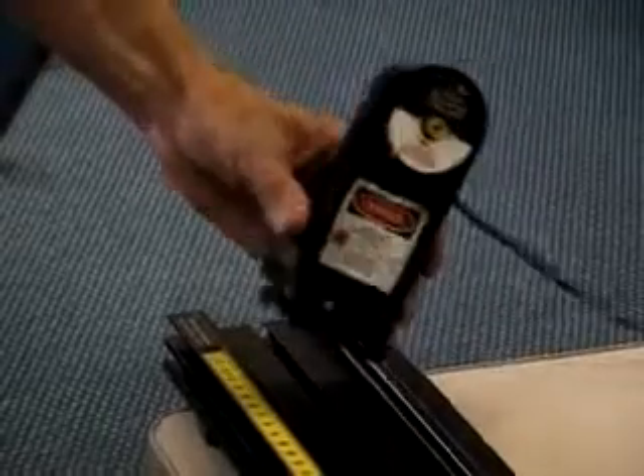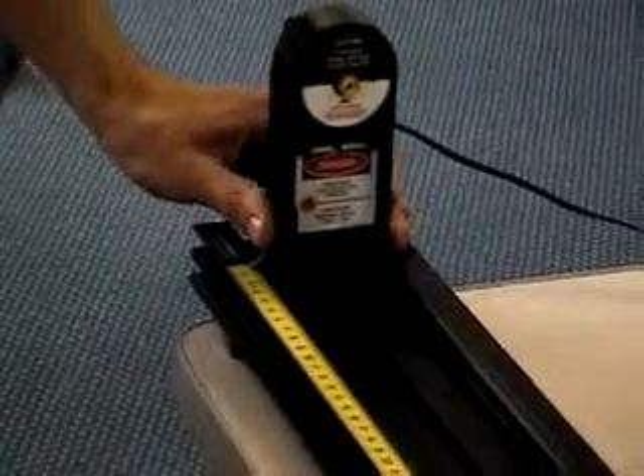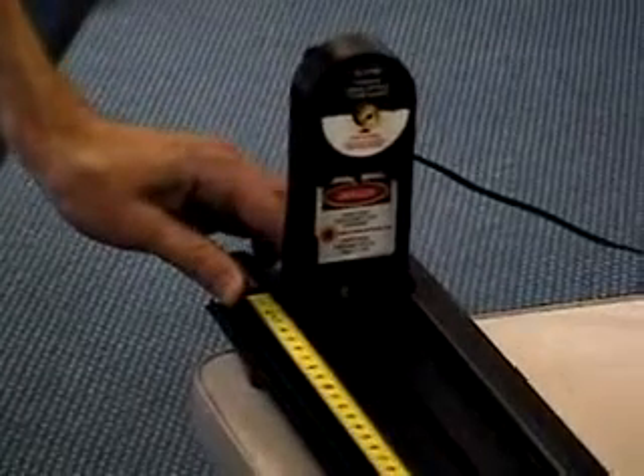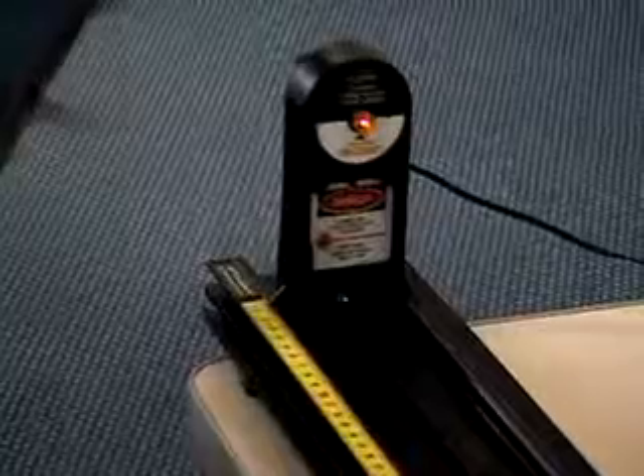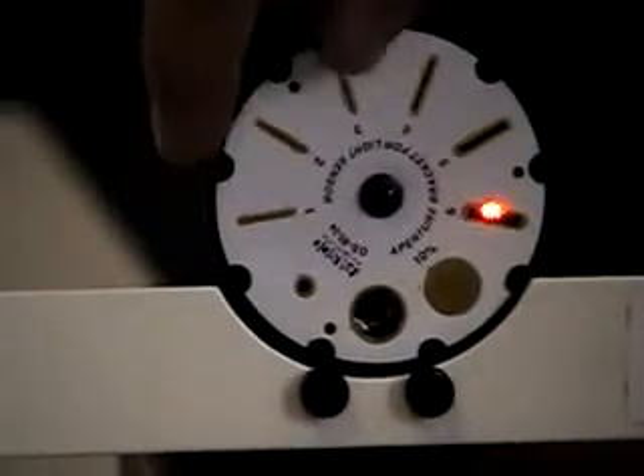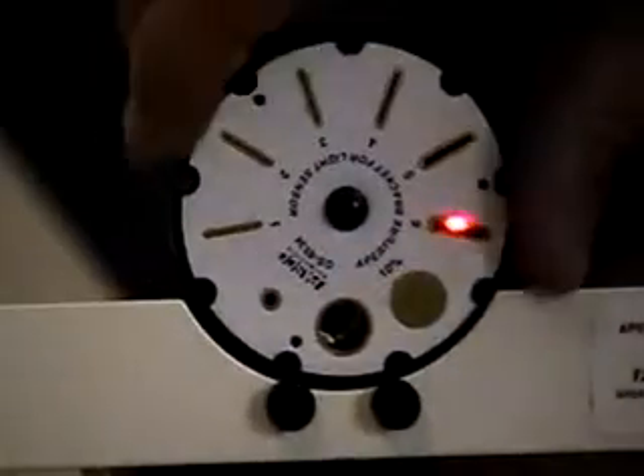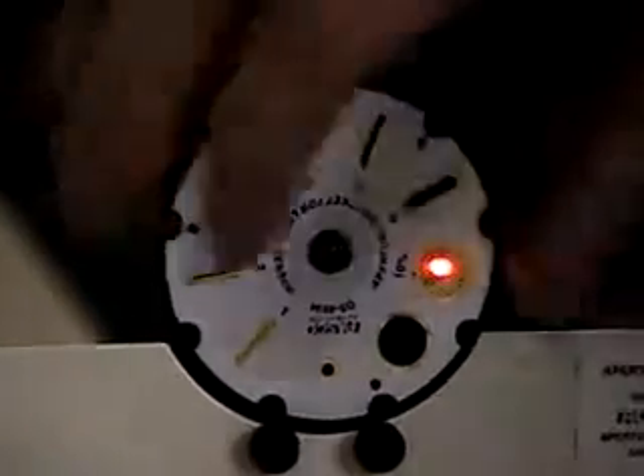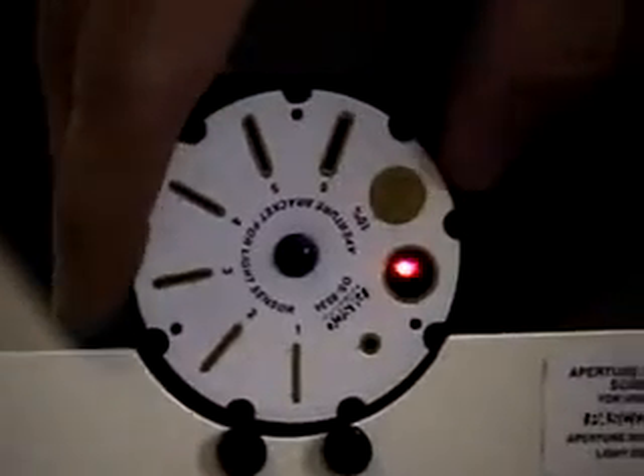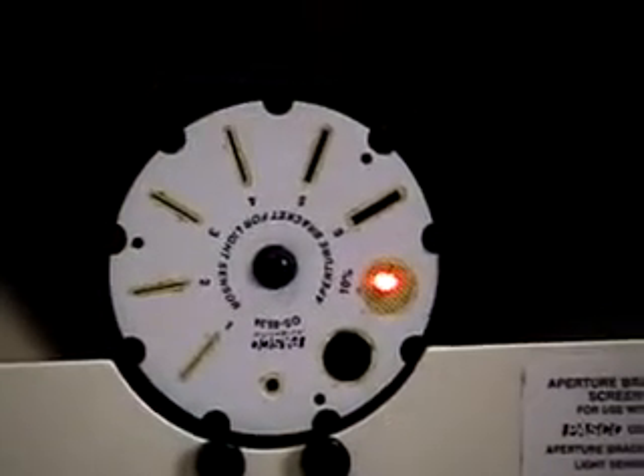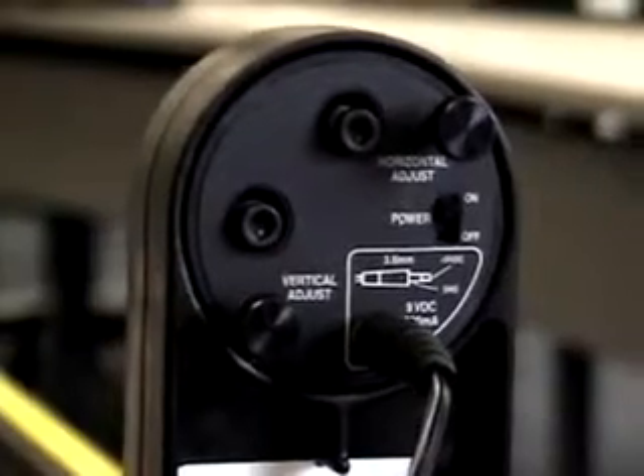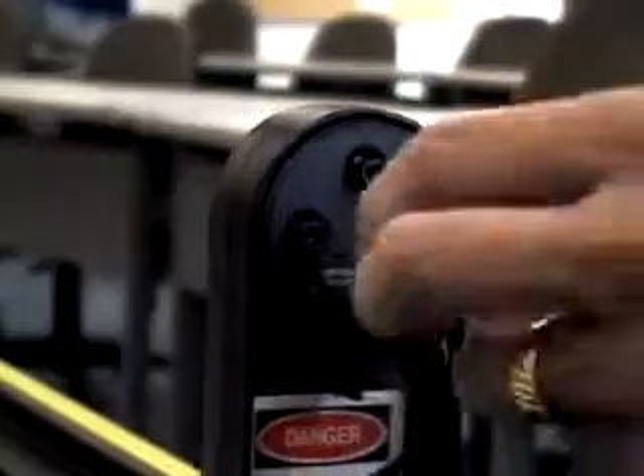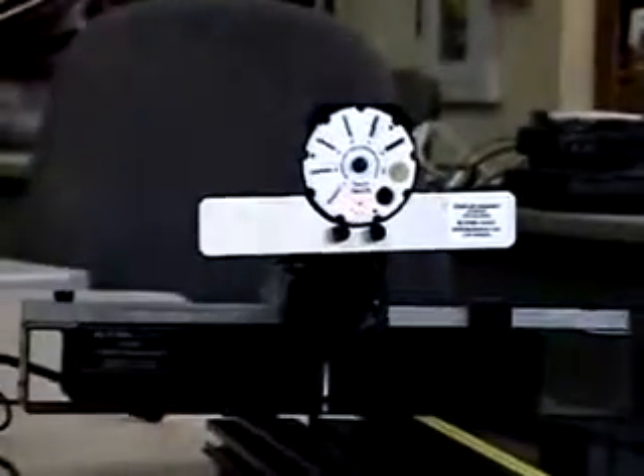So now you take the diode laser, connect it to the optics bench like that, and now we fire up the laser. Okay, so I want it to go into the opening of the light sensor there. So I usually pick one of the smaller settings, like either that hole or that setting there, and I use that to align the laser. Now to align the laser, the back of the laser has these adjustment screws here, so I can aim the beam along the X and Y axis. So what I want to do is move the beam around until I get it right in that hole.